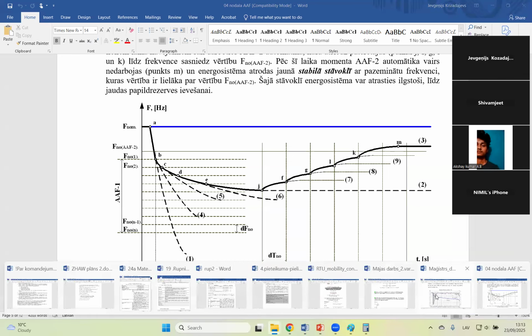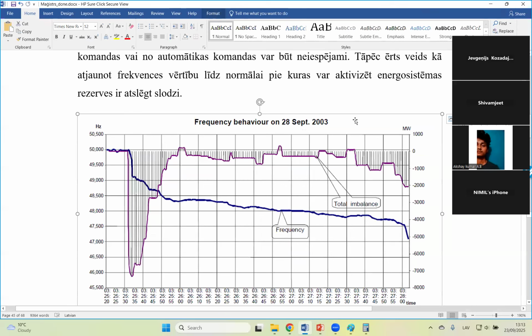And one more very important conclusion about the situation. You see that only one interconnection loss, so losing one line, leads to all the other lines being overloaded. As a result, a dangerous situation. I think this is problem number 2, because there is a very well-known criterion. It is called N-1 for power system design and operation. What does it mean, the N-1 criterion? It means that when you design and when you plan the operation mode for a power system, this N-1 criterion should be true. What does N-1 mean?